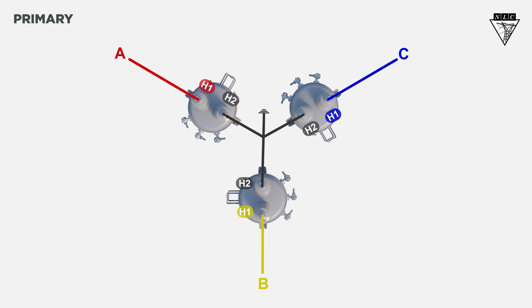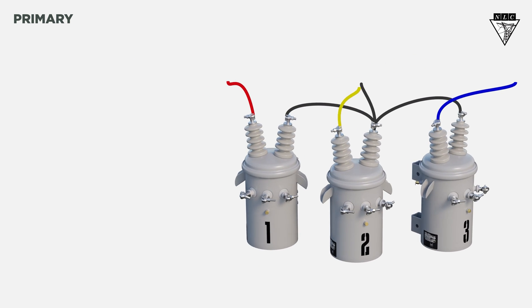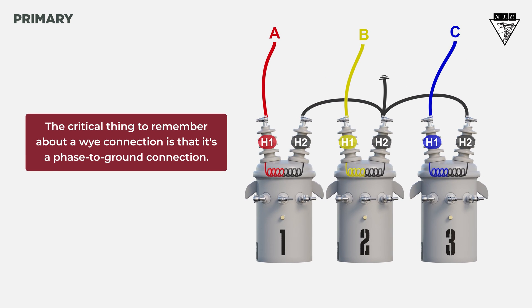Now, let's see the primary connections from the front view. The critical thing to remember about a Y connection is that it's a phase-to-ground connection. Grounding the neutral is a common practice for safety and stability reasons. Still, there could be instances where the neutral is not grounded, depending on the specific requirements of the electrical system. You can learn more about this in our other Y connection videos.